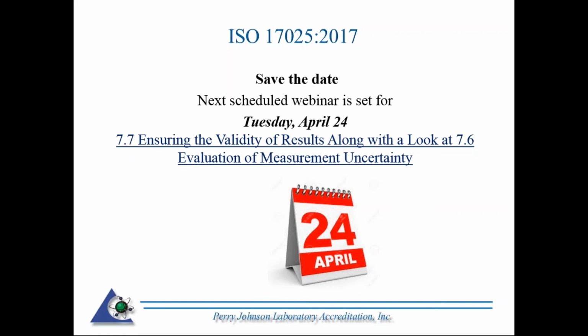Regarding calibration, you informed us that we can also follow the 6 elements of traceability. Can you provide us more detail? Well, I can't really go into all that, but I can direct you to exactly where they're located: PJLA's policy on measurement traceability, which is available on our website under resources. We go into those 6 elements and what's incorporated in them. I can tell you, if I'm looking at a non-accredited source to be approved, some of the key elements are looking at the standard that was used to calibrate your standard. Uncertainty. The source has to have a document. By definition, traceability incorporates uncertainty. And they have to have an internal measurement assurance program, i.e. they have to participate in something like proficiency testing, control charts, something like that on an ongoing basis.